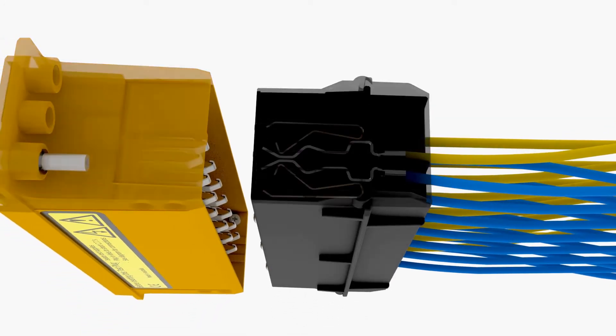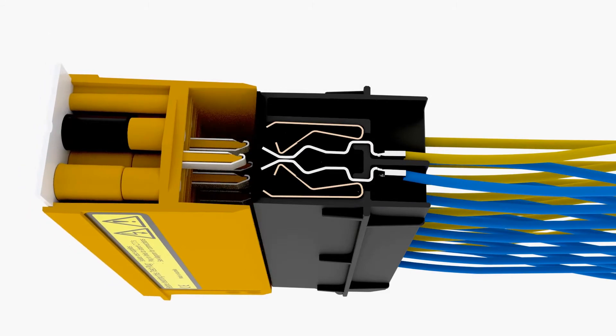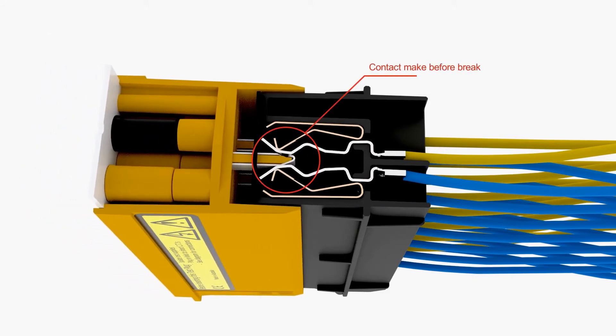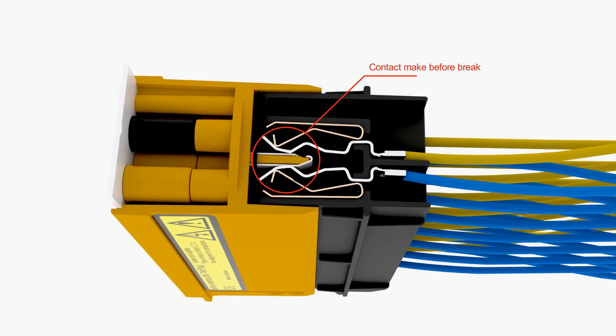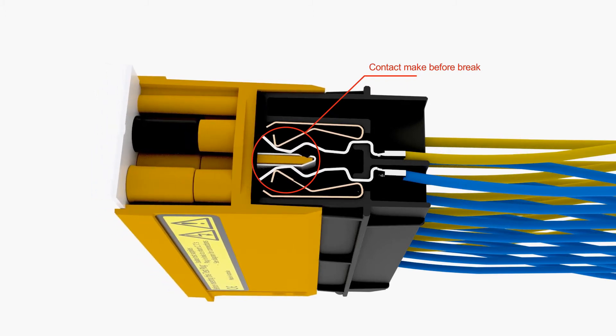To avoid open circuit conditions when the test plug is inserted, the 4M200 design ensures that contact is made between both sides of the test block and the test plug before opening the internal contact.